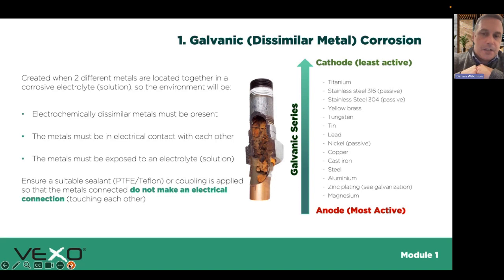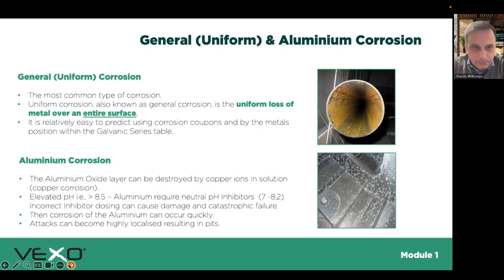But of course, one thing we can't control is if any deposits lay down on the inside of the pipework. That's a bit like imagine a contact being made across a piece of electrical equipment. Suddenly we're going to see localized corrosion taking place. So again, a lot of engineers, when they're designing systems, you typically find the metals, and if you take a look at the galvanic series there, you'll see a lot of the metals are very close together for the most part on that galvanic table.